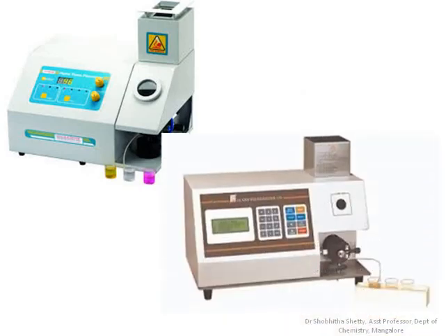As you can see, this is the instrument that we use in the laboratory, where you can see the inlet here. The sample is placed in the form of its metal ion solution, and the capillary is inserted through the nebulizer, and the sample is taken near the flame. Inside the flame photometer we have the flame source here, and during the interaction with the flame there will be excitation followed by the emission process, and this emission intensity is displayed based on the emission pattern by different elements.